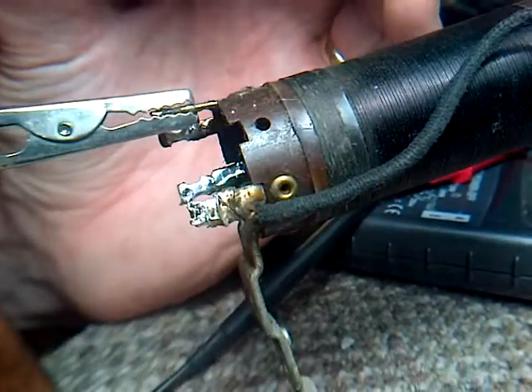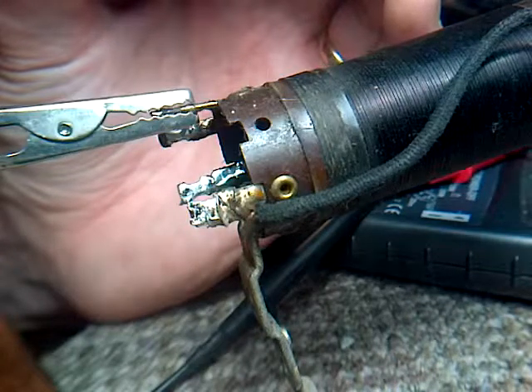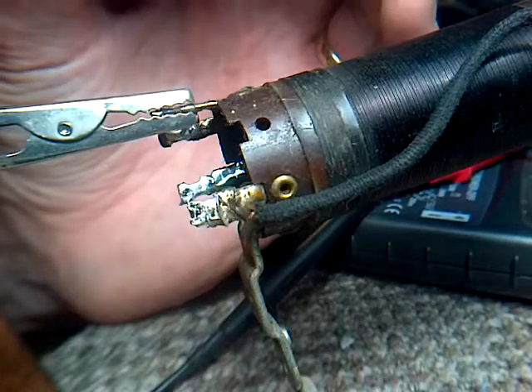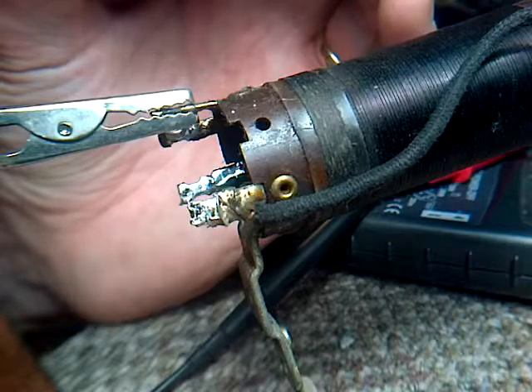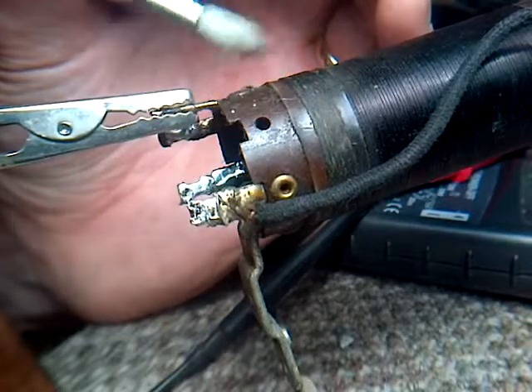So what do I do if I find a break in the wire? One break in the wire — I have to fish the ends out and then splice in a short length between the ends. If the break is right near the end of the coil, you can just do away with a turn.